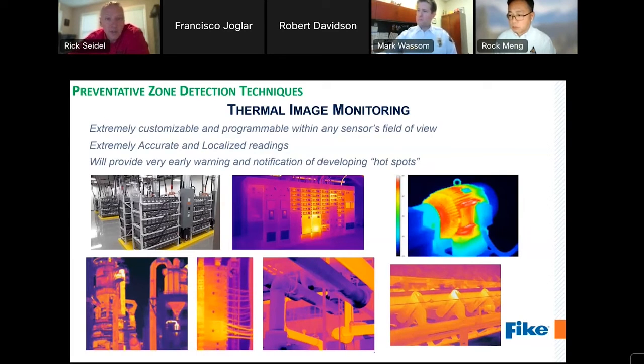We can tie the thermal imaging system directly into the BMS to initiate rack or cell disconnect, but will not typically use a thermal image notification to activate an extinguishing system or to signal the building fire alarm, as a fire has not yet definitively occurred and we are trying to prevent it from occurring. One shortcoming of thermal imaging is that it is limited to line of sight from the sensor, and most energy storage system units are typically packed extremely full and tight of cells and racks, thus limiting the line of sight of any sensor.